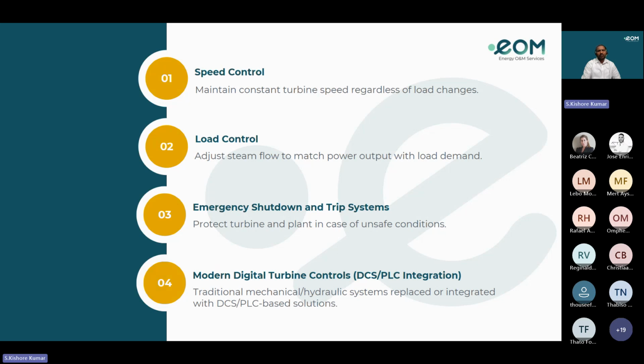Coming to the governing systems, there are speed control, load control, emergency and trip systems, and modern digital turbine controls. In speed control, the objective is to maintain constant turbine speed regardless of load changes. Whereas in load control, the objective is to adjust the steam flow to match power output with respect to the load demand. The emergency shutdown and trip systems protect the turbine and plant in case of unsafe conditions. In modern digital turbine controls, with DCS or PLC integration, traditional mechanical hydraulic systems are being replaced or integrated with DCS or PLC based solutions for faster response.